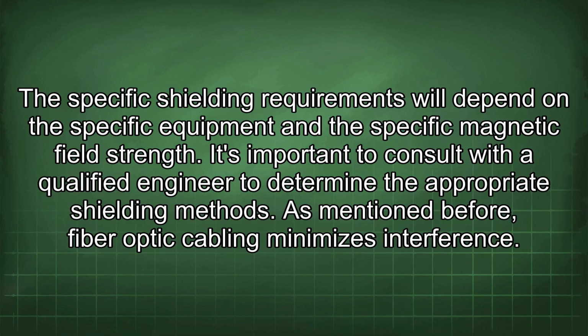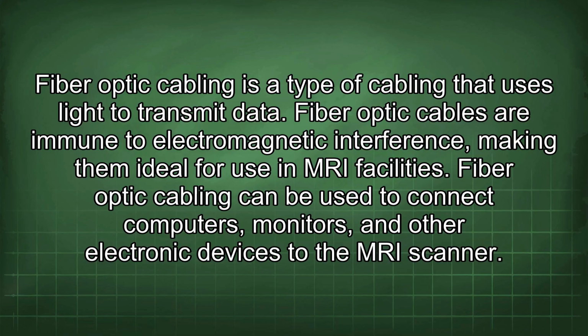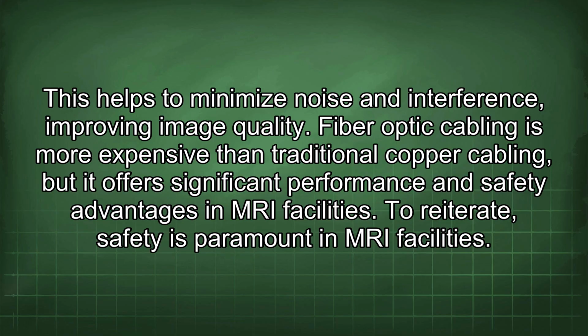As mentioned before, fiber optic cabling minimizes interference. Fiber optic cabling is a type of cabling that uses light to transmit data. Fiber optic cables are immune to electromagnetic interference, making them ideal for use in MRI facilities. Fiber optic cabling can be used to connect computers, monitors, and other electronic devices to the MRI scanner. This helps to minimize noise and interference, improving image quality. Fiber optic cabling is more expensive than traditional copper cabling, but it offers significant performance and safety advantages in MRI facilities. To reiterate, safety is paramount in MRI facilities.